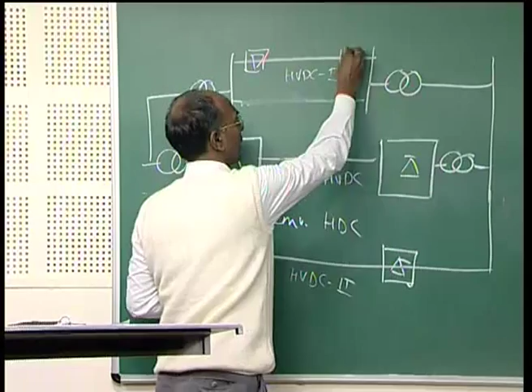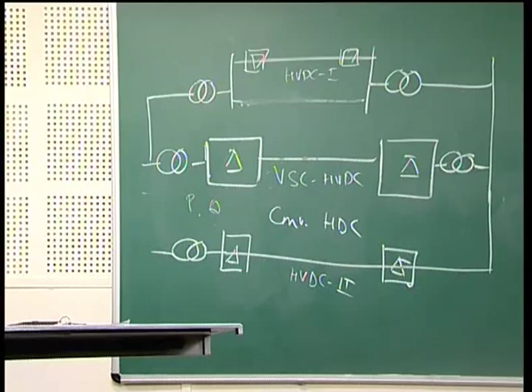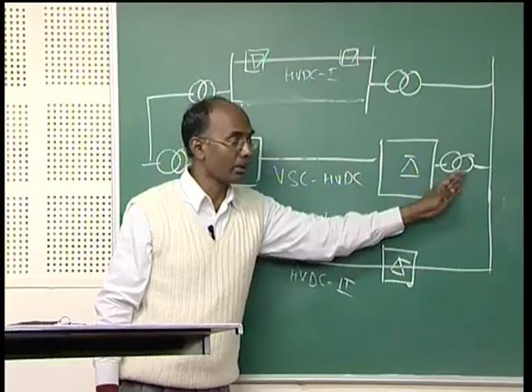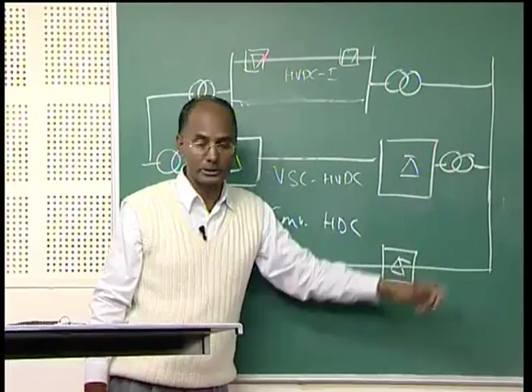I mean to say that with buried cables there are no electromagnetic fields, and there is freedom from oil leakage, since there is no oil. So, there is no oil leakage, it has a low impact on the converter station structure, and also no electromagnetic fields. I mean to say that if it is buried, and also if you have the anti-parallel arrangement, the impact of this electromagnetic radiation is going to be very small. The cables are operated in the bipolar mode, as I said. Bipolar means one conductor is go and another is come: one cable with positive polarity, another with negative polarity, so the whole magnetic field is going to be minimized.